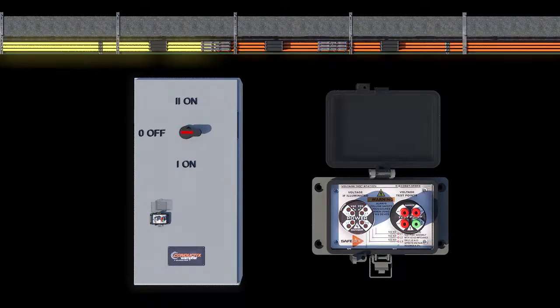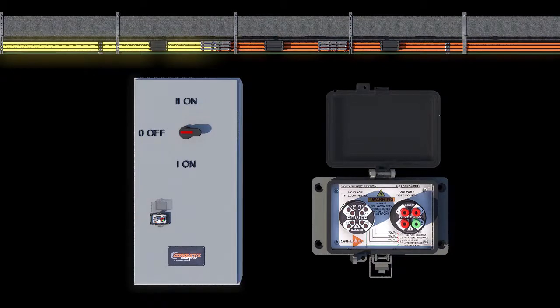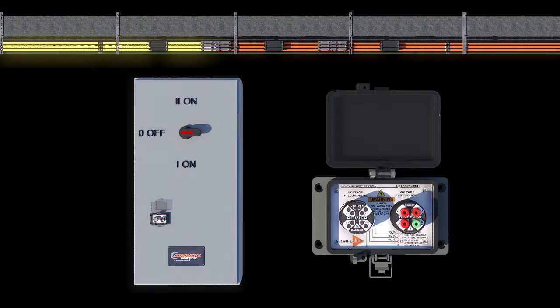This removes power from the buffer zone and the maintenance zone. The voltage indicator lights and the test points should be off and read no voltage.